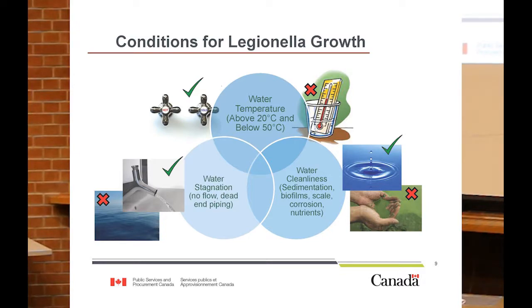And then stagnation, water stagnation. We want to avoid having dead legs in our systems and also avoid low flow or no flow conditions. One thing we often have to discuss with some of our energy-focused engineers is on the domestic hot water side, where they often talk about turning down hot water tank temperatures and/or shutting off recirculation pumps on weekends to save energy. There we want to make sure the water continues to flow, and also that when we're generating hot water, it's actually hot and not within the growth temperature range.